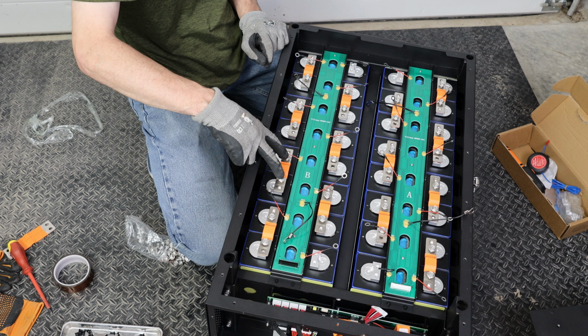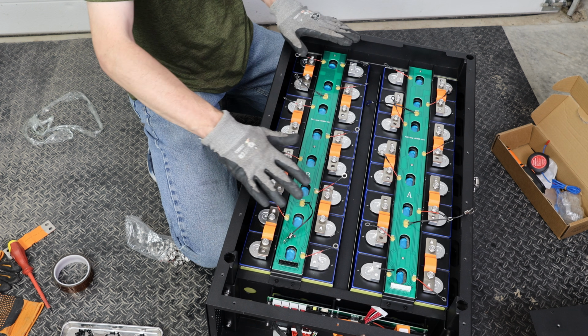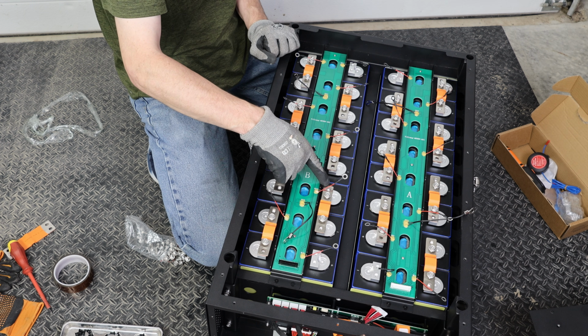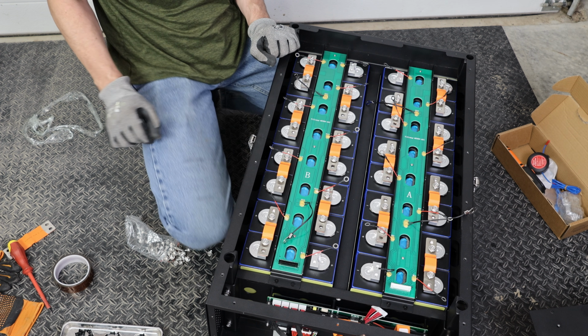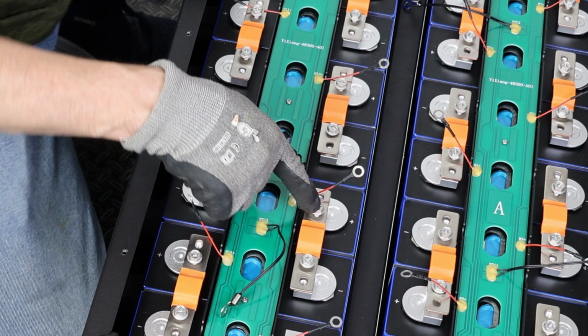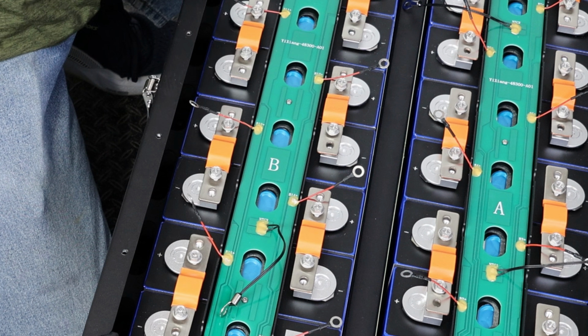I've temp set the inner bolts on all of the bus bars. Now I can connect the sensor wires to the remaining open locations. That way we always have 1 connection that isn't shared with a sensor wire.